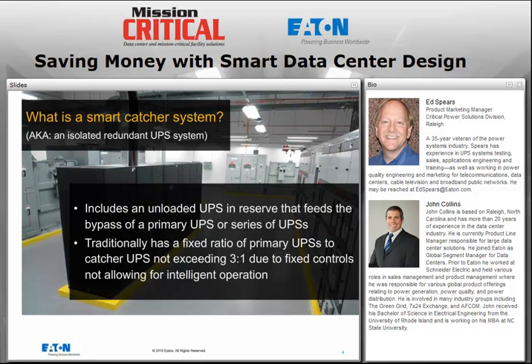So let's take a look at what we call a smart catcher system, again, otherwise known as an isolated redundant UPS system. And this is the type of system that includes an unloaded spare UPS held in reserve, and its output feeds the primary UPSs or multiple UPSs through their bypass feed. So in other words, instead of a UPS transitioning to plain utility power for maintenance or on a failure, it actually uses the output of the catcher UPS.